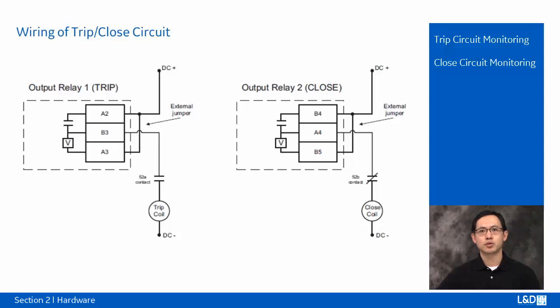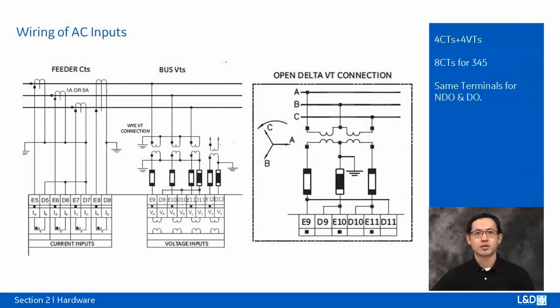If the trip or close coil circuits get disconnected, or if in general a high resistance is detected in the circuitry, a trip or close alarm will be set and the alarm and maintenance LEDs will be on. 350 and 339 relays have 4 AC current inputs and 4 voltage inputs. The 345 relay has 8 AC current inputs. The terminals are from E5 to D12, the same for the drawout and non-drawout.